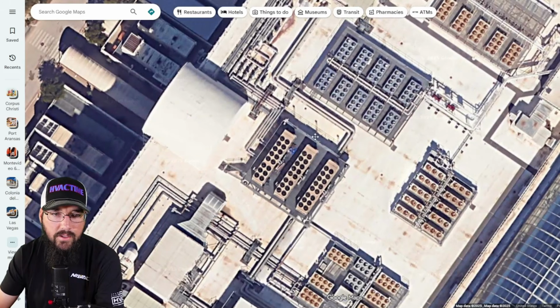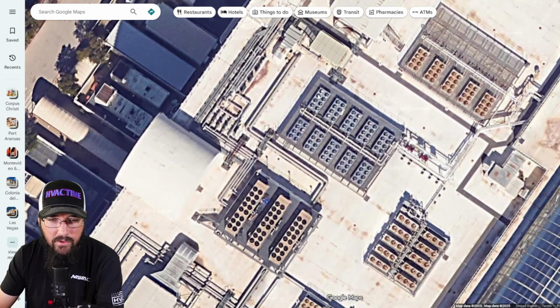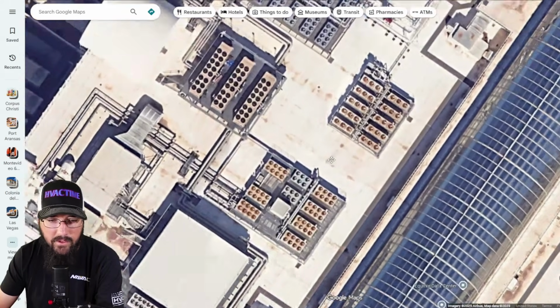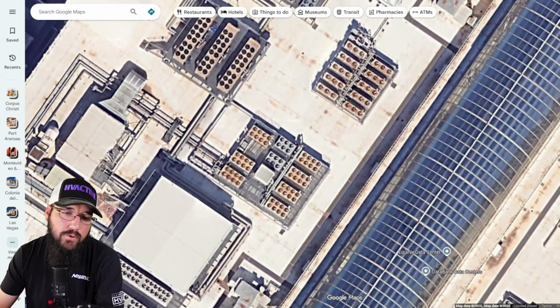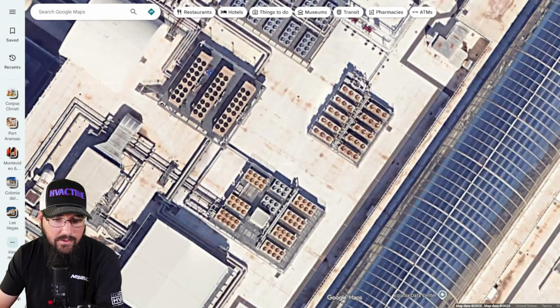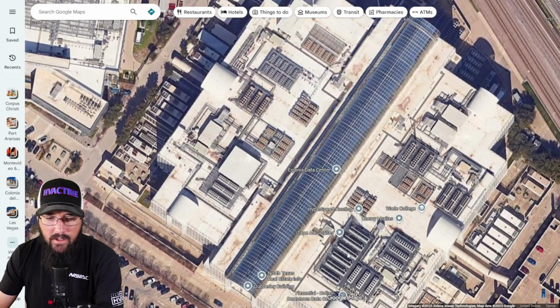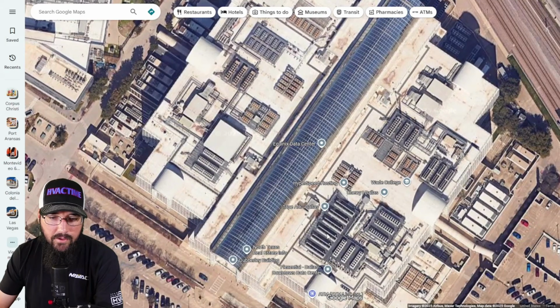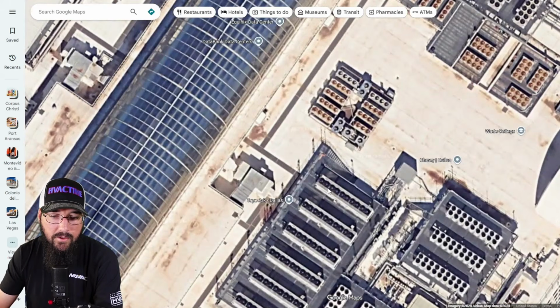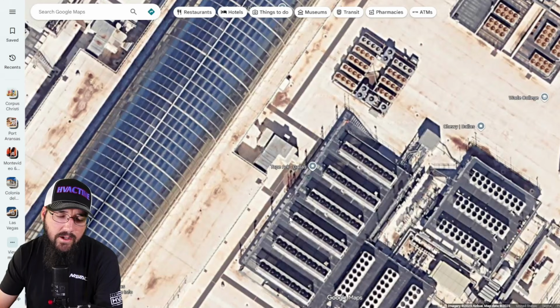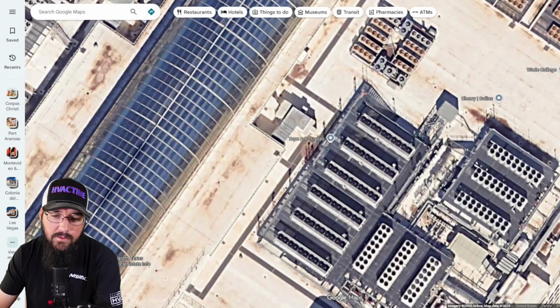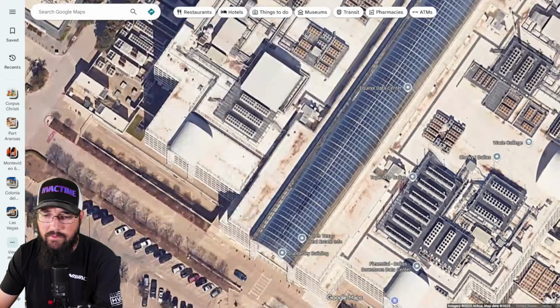That's not something you have to identify, I'm just saying that's what I'm seeing. These look like they could be some Carrier machines, looking at the shape and color. These old rusted things might be Trane - Trane has the steel condenser fan blades, that's one of the things you'll see common with those. These look like they could be Smardt right here, to be honest, or maybe some newer Trane units. These could be a newer Trane, but those are only single line, so those may not be air-cooled chillers, but these for sure I'm very confident are.